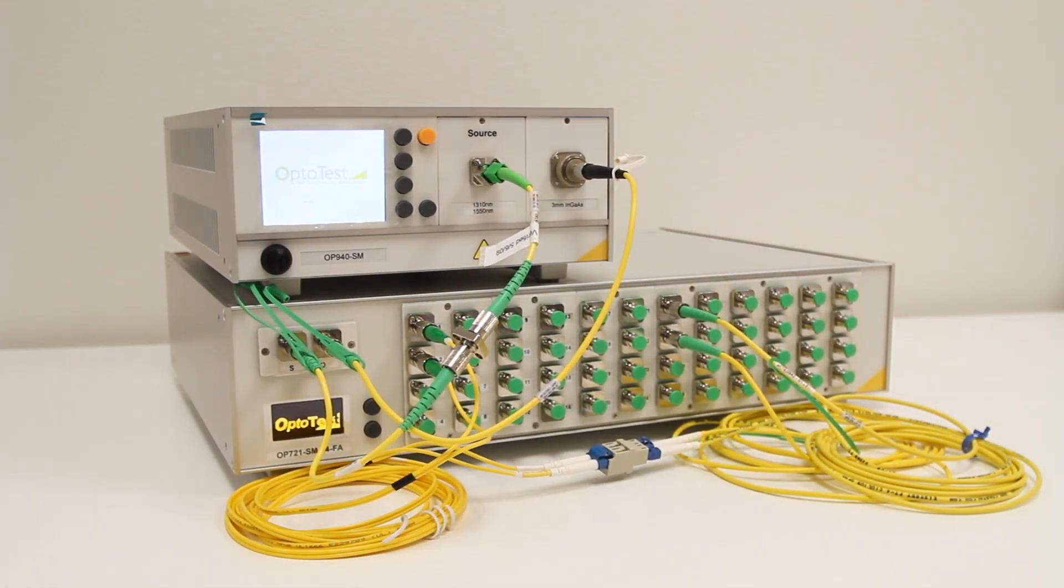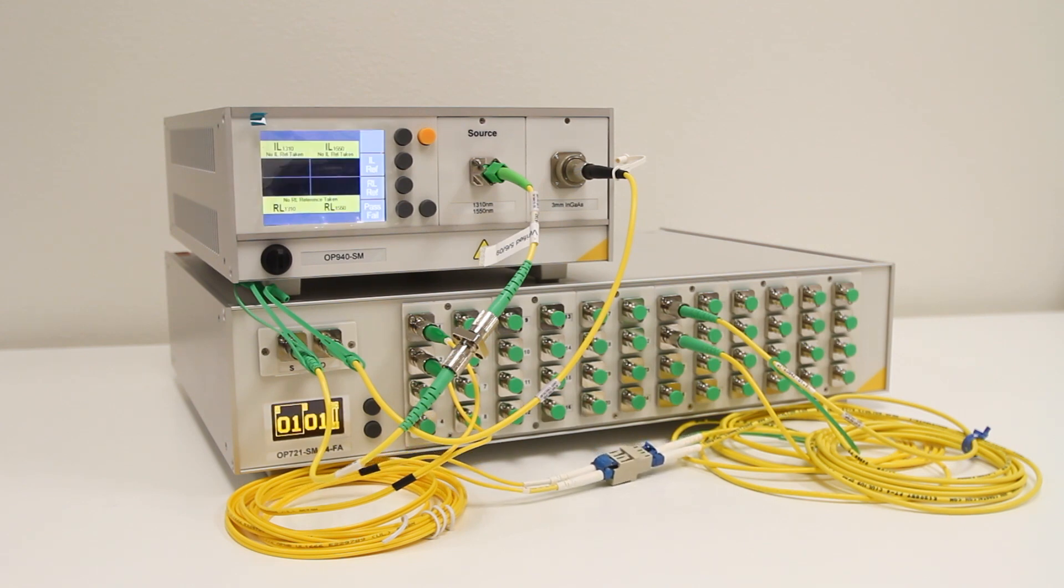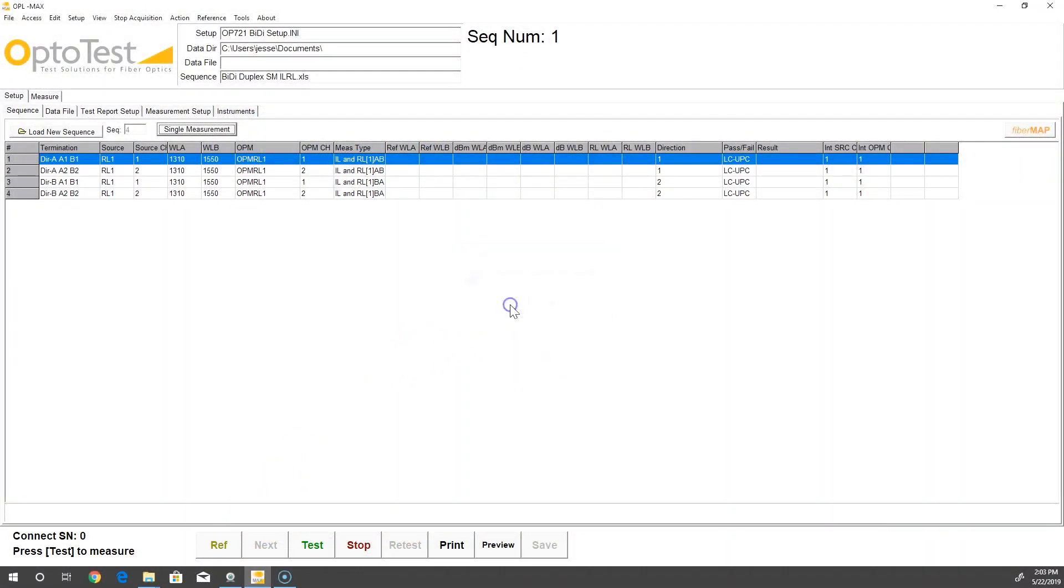Once the units are powered on, we can begin testing in OPL Max. We obtain insertion loss reference values for channels 1 and 2, first in the forward direction, then in the back direction.